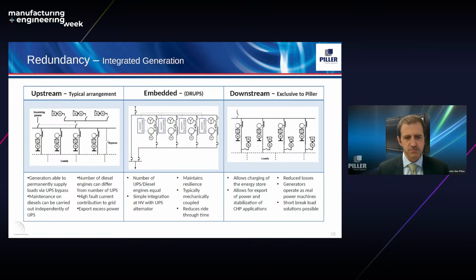Finally, downstream. This is unusual, and not all UPS can do this. With DNO networks that are really overstretched, and stressed as we talked about earlier, this solution can allow overloaded grids to integrate where there are limitations on connection capacities due to the isolation between the generation and the main connection.